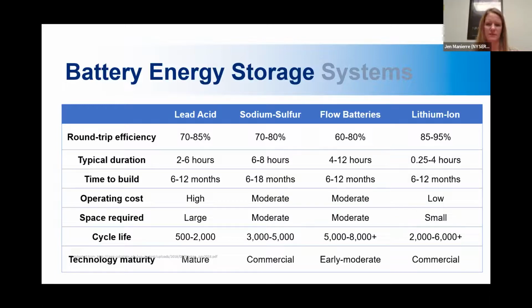The time to build for all of these different types is right around the same amount of time. However, in the middle here for the operating cost, you see that lithium ion has a low operating cost, which is very important, right? We want to be able to provide these services cheaply. So low operating cost is great. Another thing that sets them apart in the next line down, the space required, is that they have a very small space requirement. You can pack a lot of energy into a very small space with lithium ion batteries, which is great. Cycle life is right around average with the others, and the technology maturity for lithium ion batteries is up there. They're very highly commercialized. So when you add all of that up, you can start to understand why lithium ion is starting to dominate the market for battery energy storage.